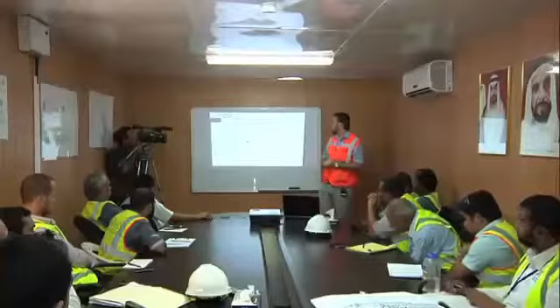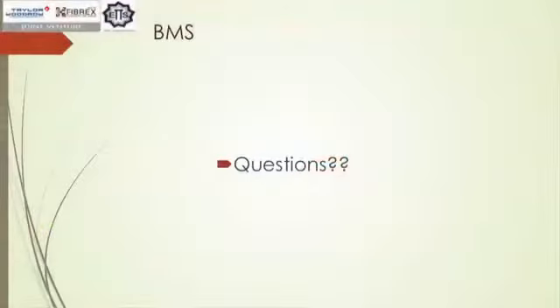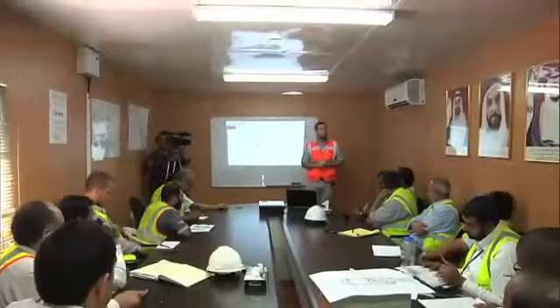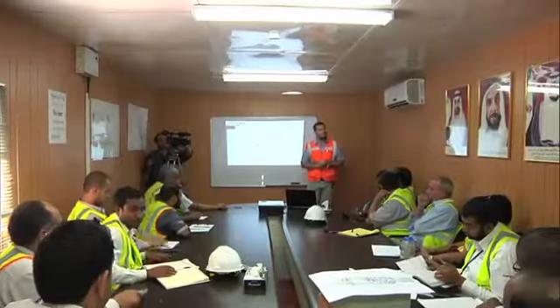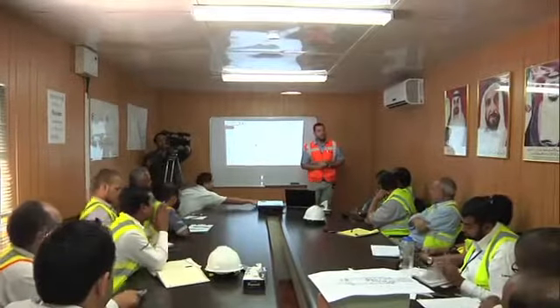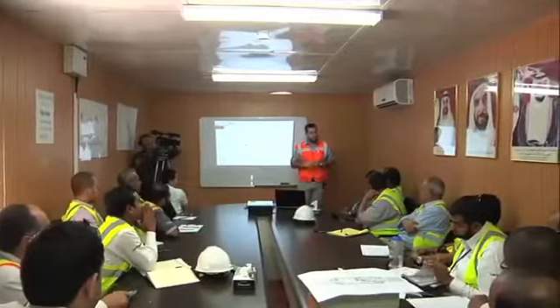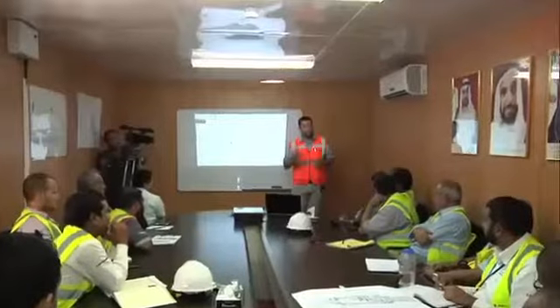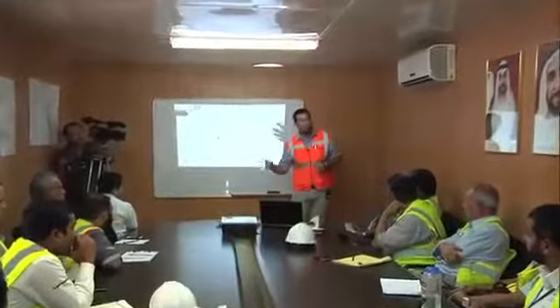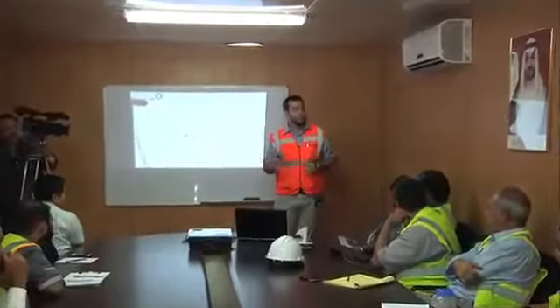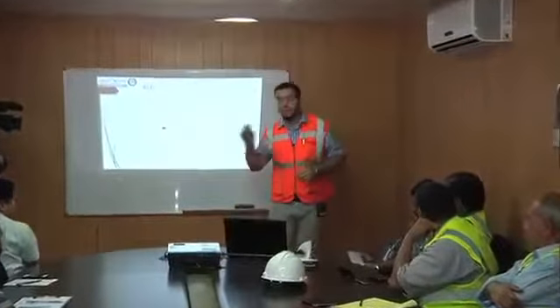Visual, and I guess, yeah. Any questions regarding BMS? So these SMDBs, DBs, all monitored by the BMS? Yes, yes. And for the SMDBs, no, there is no control. You cannot switch on the breaker with BMS, right? So it will only show you that this breaker is tripped, or it will give you the alarm, or this SMDB is not active, or that is not active.